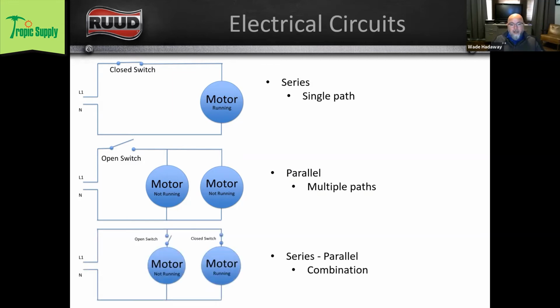And then we've got a series parallel circuit, which is a combination. So we have two motors. Each motor is wired in parallel. And then in series with each motor, we have a switch. Typically, in residential heating and air, our switches are either safeties or a thermostat, right? Typically, we've got low voltage switches. Our loads might be low voltage. It might be high line voltage. And we'll go over that here in just a minute.